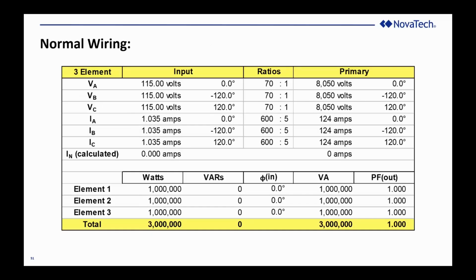So here's a normal scenario we start with. I invert the A and the B phase, or the B and the C phase, or the A and the C phase, doesn't matter which two I invert. By typing in the 180 in the bottom half of the page, you can see the A phase is now 180, and the B phase is now minus 120 plus 180, which equals 60, and the C phase is still plus 120. When you do the vector math, you now see the two inverted phases are minus, the third phase is plus. You still get twice the neutral current. You still get 1/3 of the total watts. The watts is 1/3 of the VA. All good indicators that if that's what you're looking at on a multifunction meter, that's the kind of wiring error that caused it.